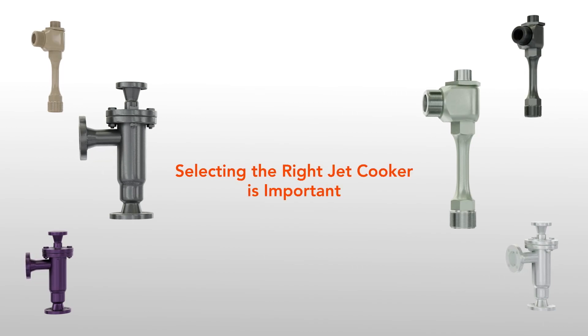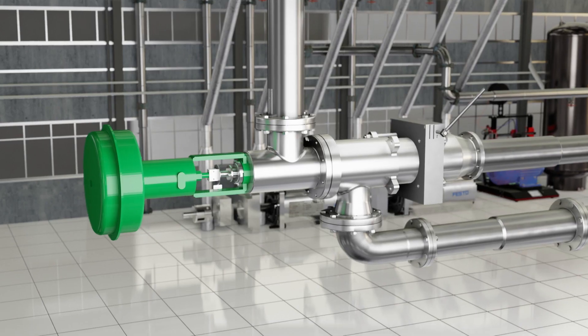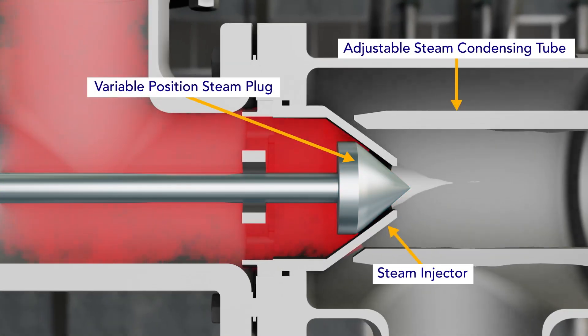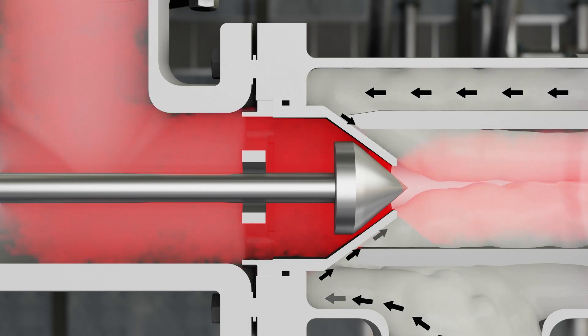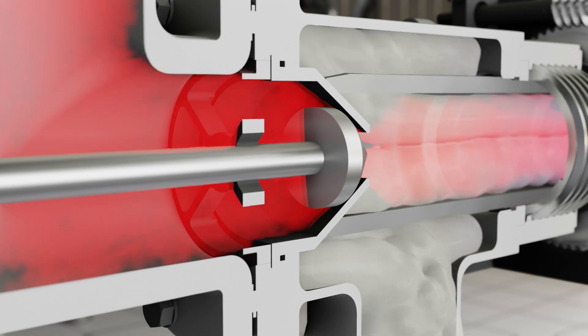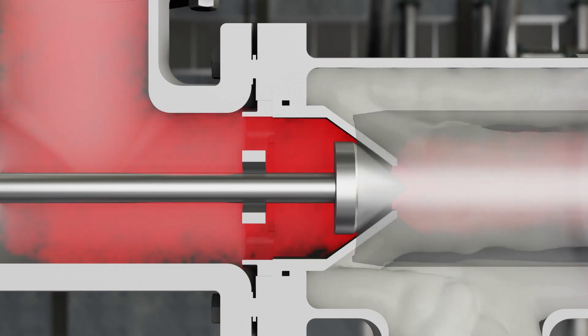Selecting the right JetCooker for your starch cooking process is important. Not all steam injectors meet the design requirements for starch jet cooking. A true jet cooker has a coaxial steam injector and an adjustable condensing tube. The steam flow can be varied while maintaining high injection velocity, and the tube adjustment varies the slurry gap opening. Adjusting the steam condensing tube changes the gap opening to ensure a uniform ribbon of starch slurry enters the steam injection mixing zone.